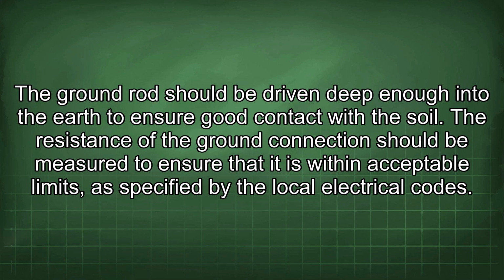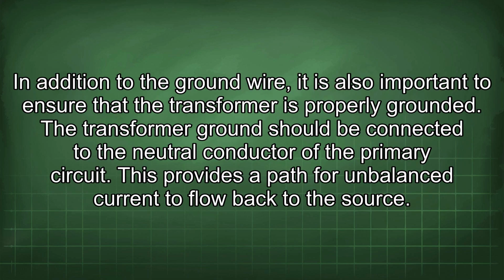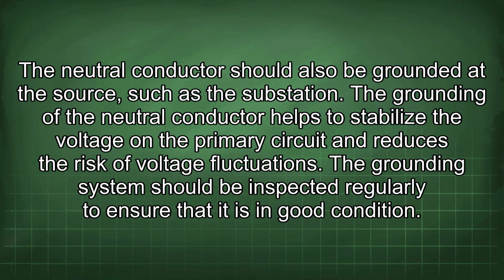In addition to the ground wire, it is also important to ensure that the transformer is properly grounded. The transformer ground should be connected to the neutral conductor of the primary circuit. This provides a path for unbalanced current to flow back to the source. The neutral conductor should also be grounded at the source, such as the substation. The grounding of the neutral conductor helps to stabilize the voltage on the primary circuit and reduces the risk of voltage fluctuations.